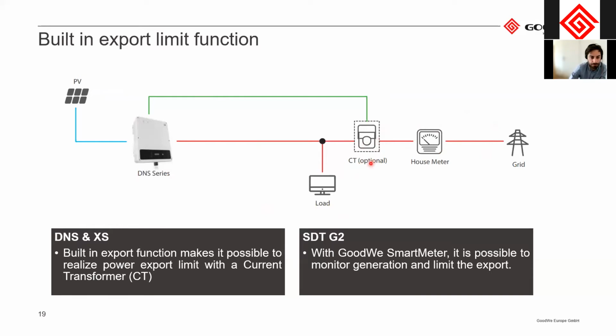For the three-phase inverter, this is not completely built in. The function is still built in, but you need to have a smart meter, which is slightly larger than the CTs. So it's an additional device here to which the CTs are connected, and then the smart meter is connected to the inverter.